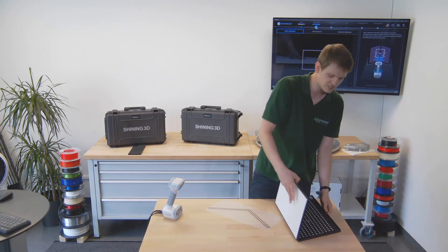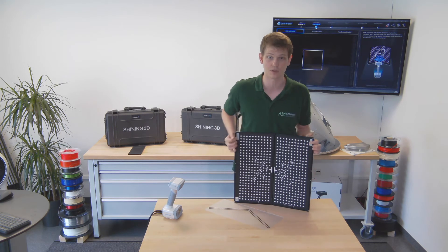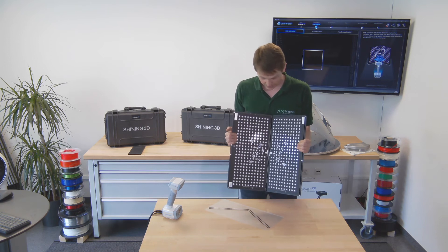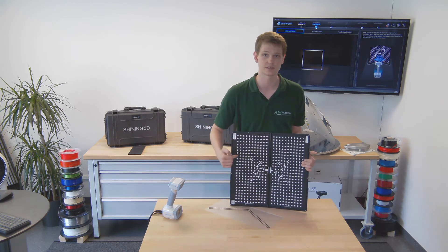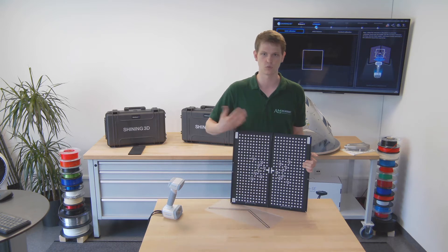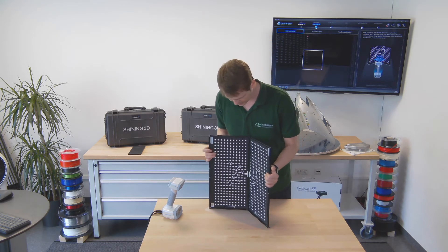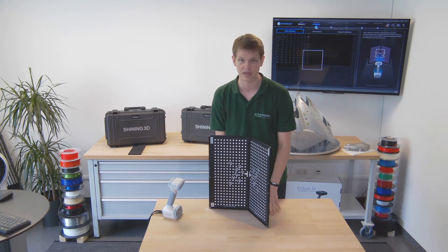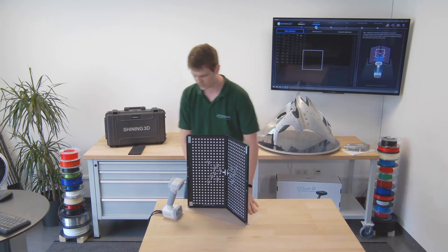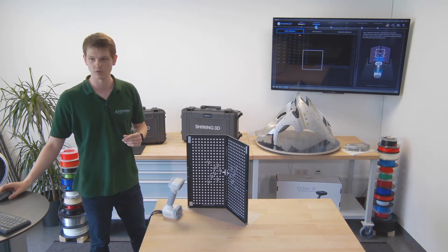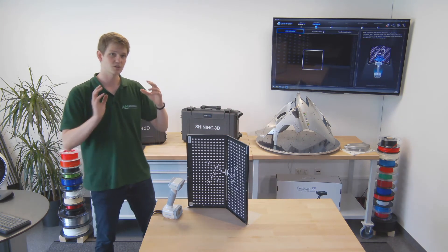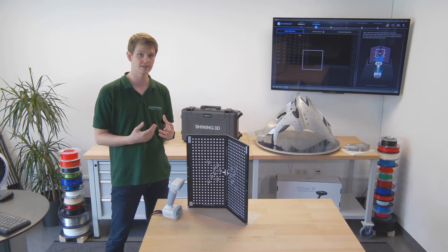The calibration board is specific to your scanner—it's matched by a serial number in the top corner, so I cannot use this board with a different scanner. There are little frames at the bottom that have to face down to give you orientation. I place it with those areas facing downwards onto the guide that demonstrates what angle I should have it at, then simply follow the on-screen instructions.